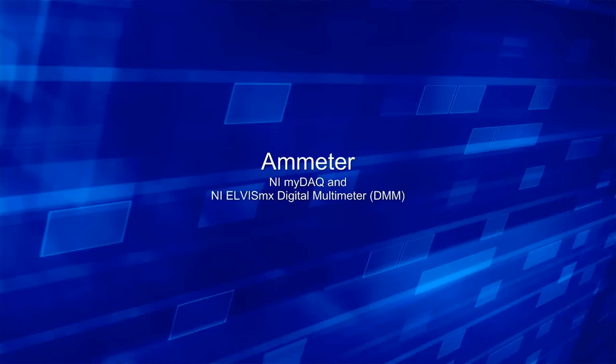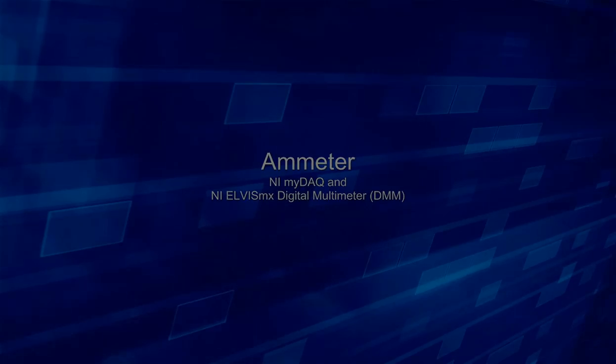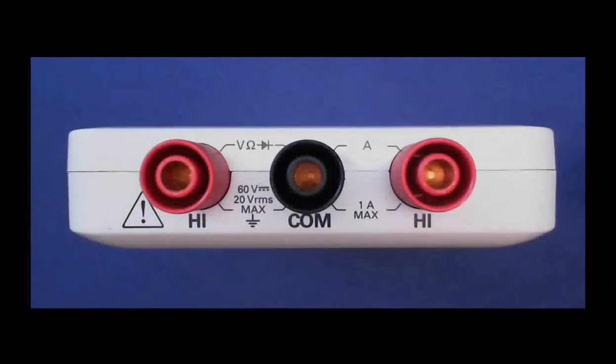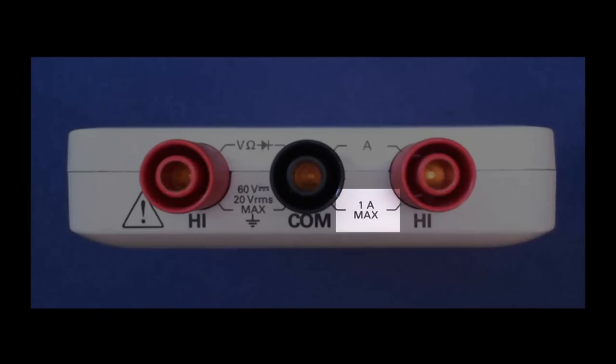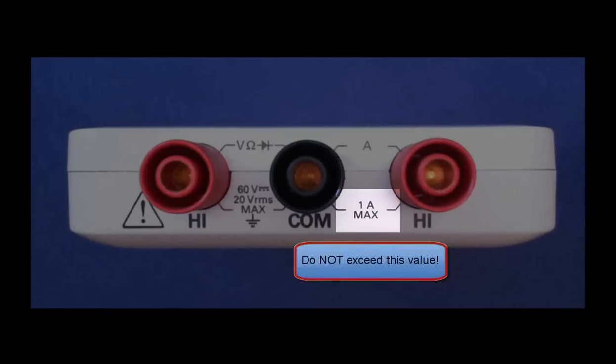Let's learn how to use the ammeter function of NI myDAQ. Anytime you use the ammeter, pay attention to this maximum specification. Do not subject myDAQ to more than 1 amp of current.